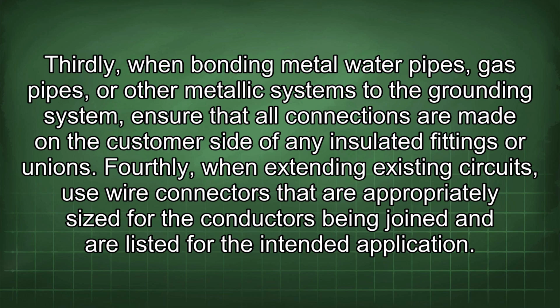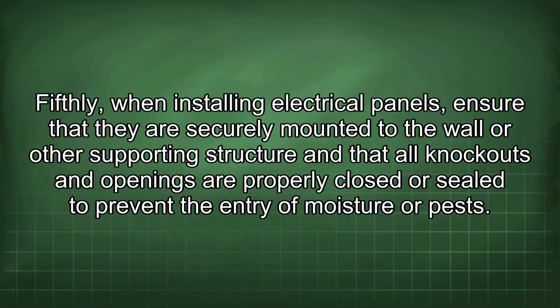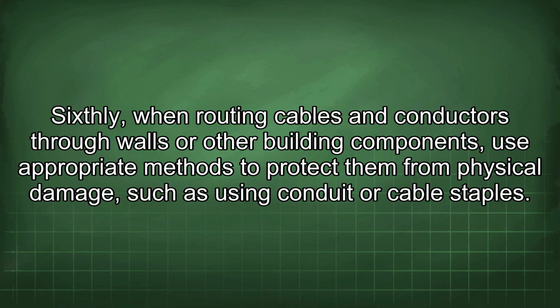Fourthly, when extending existing circuits, use wire connectors that are appropriately sized for the conductors being joined and are listed for the intended application. Fifthly, when installing electrical panels, ensure that they are securely mounted to the wall or other supporting structure and that all knockouts and openings are properly closed or sealed to prevent the entry of moisture or pests. Sixthly, when routing cables and conductors through walls or other building components, use appropriate methods to protect them from physical damage, such as using conduit or cable staples.